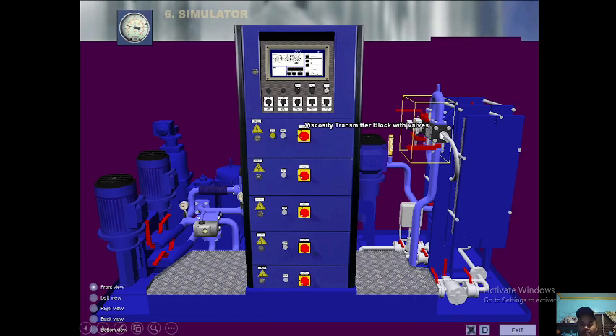So if the viscosity is high, then it means it needs more heating. So it will send a signal to this valve to increase or decrease heating, depending on the viscosity that it is reading. Okay, so this is the valve that will be controlled, and if there is damage on this valve, there is a bypass valve also. And then on the return side of the steam, we have here a steam trap, and if ever there is damage in the steam trap, or during maintenance maybe, we can also use the bypass valve.